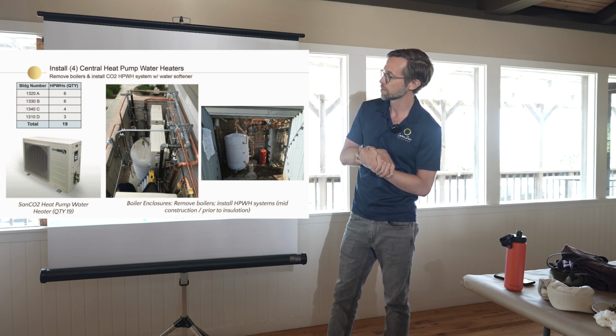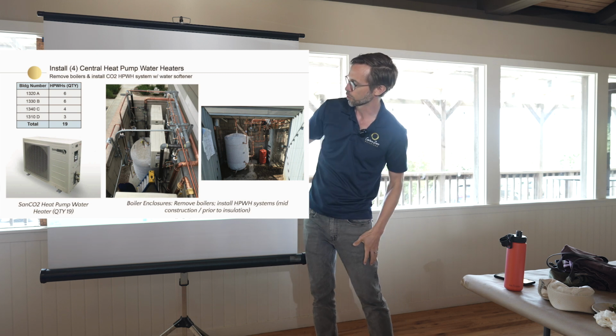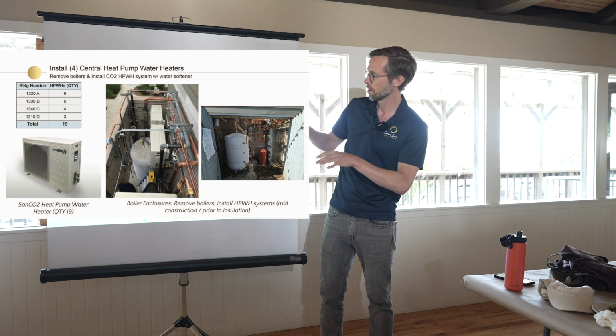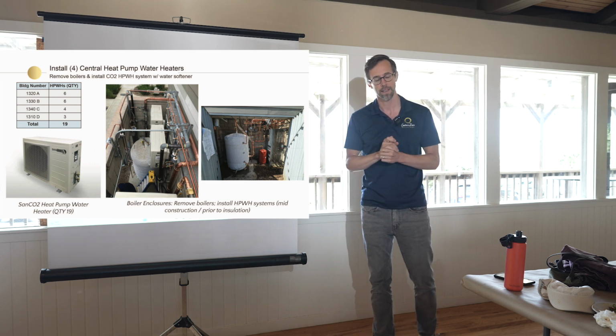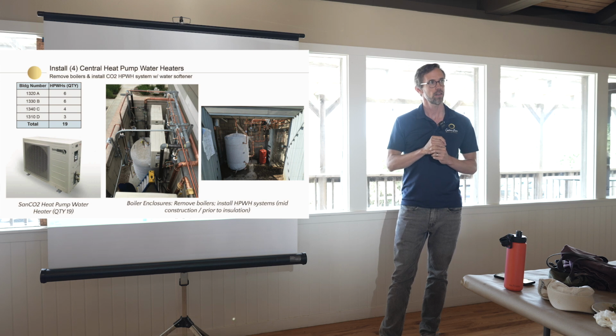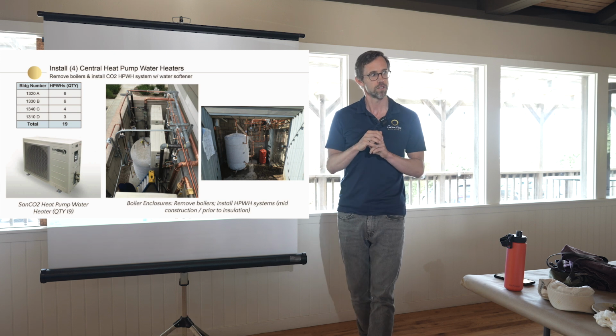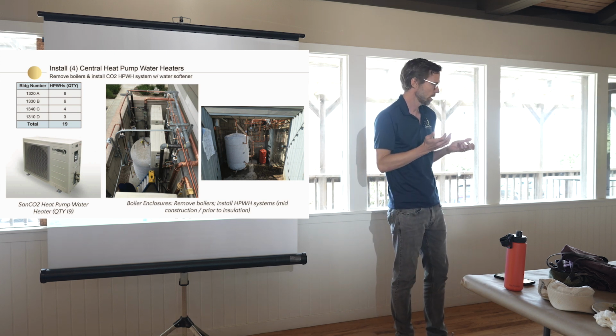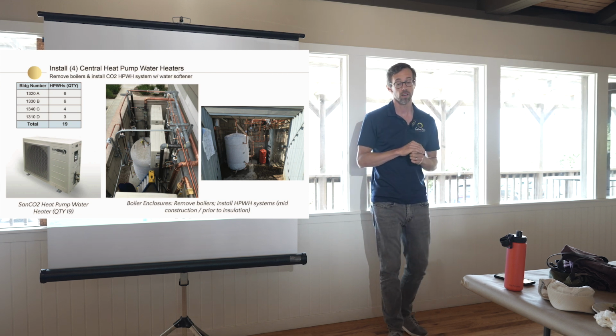And we did some really creative 3-dimensional work because this is like a roofless enclosure here, and the tanks are down low, and they have way oversized their existing piping. God, the ASPE code on pipe sizing, I can't wait until it changes, because you see this is a 32-unit building with 4-inch cold and hot supply pipes, 4-inch, which is insane. I mean, they really only need like 1.5 inches. I mean, and what does that mean?